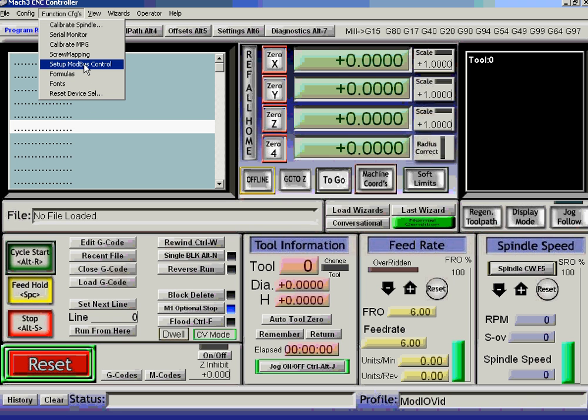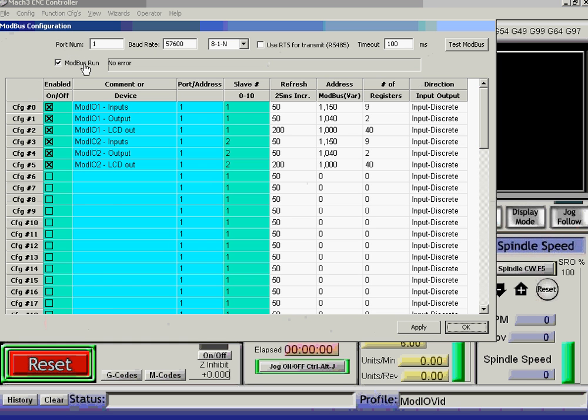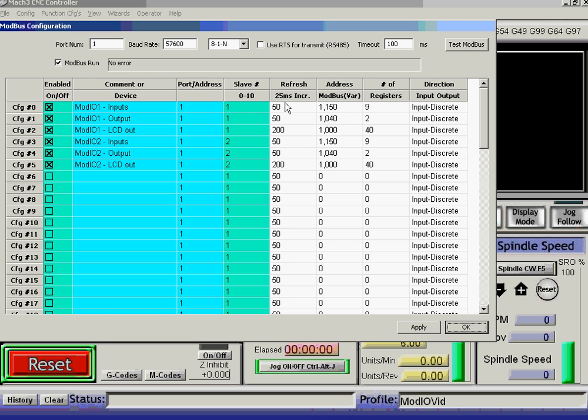Just before we exit this video, let me show you how the table that was blank has now got filled. We've got the name of the device, and it's got inputs, outputs, and because we enable the LCD, it's got the LCD. They're enabled. It tells us what slave they are. It tells us what refresh rate we're at. We set both of them at the high speed refresh rate.